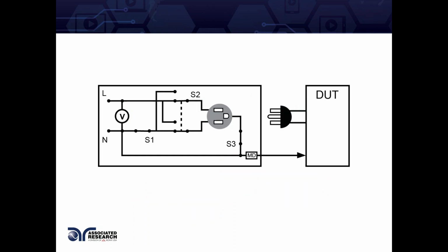So let's go back to our fault conditions. As I said, most modern leakage current test analyzers are capable of simulating the fault conditions that we've talked about internally.